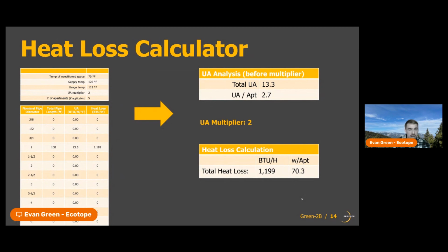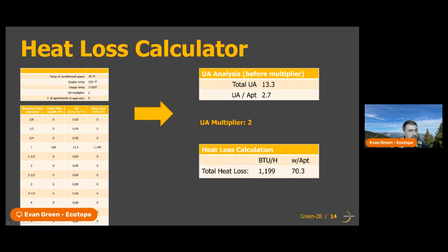So in order for you to not have to run the heat loss calcs for every section of pipe, because it does change as the pipe changes in size, I've created this calculator that is actually a lot like Christoph's calculator. I'm happy to report we get the same answer when we're plugging in different pipe lengths and sizes. I created this calculator for BPA; it has very simple inputs and makes some assumptions to be able to calculate this overall heat loss. Some of the inputs we'll need to make are the temperature of the conditioned space, which is about 70 degrees to make people comfortable, the supply temperature, which is the water temp leaving the mixing valve, and the usage temperature, which is the temperature leaving the tap.